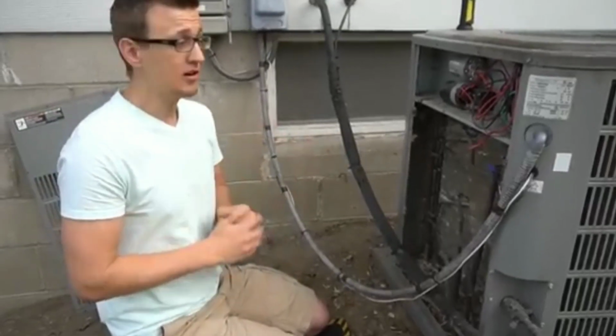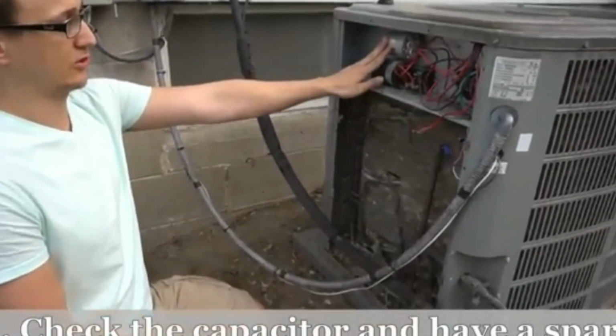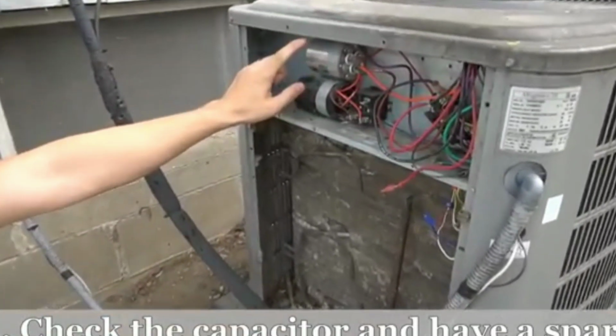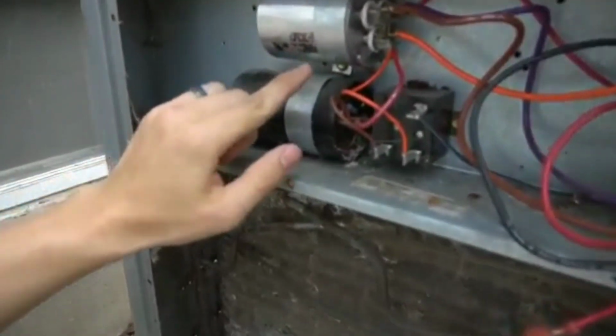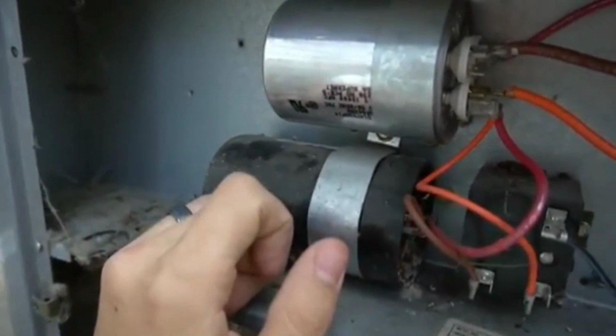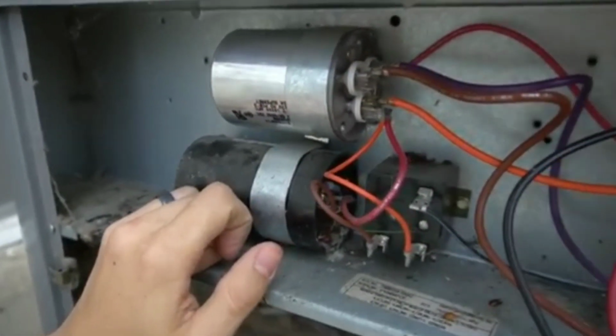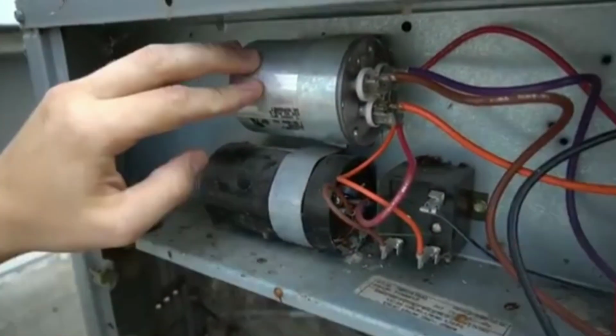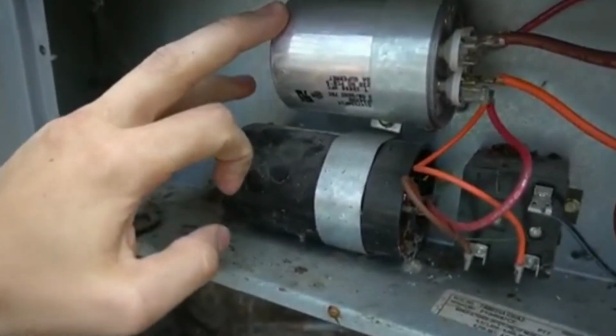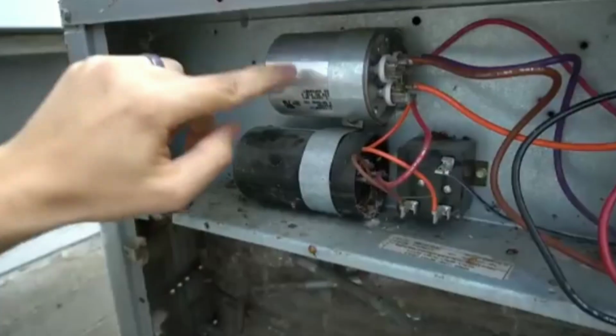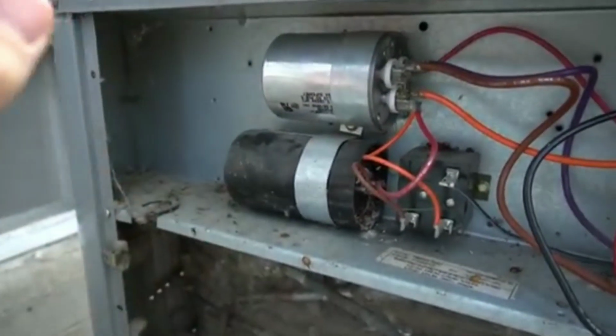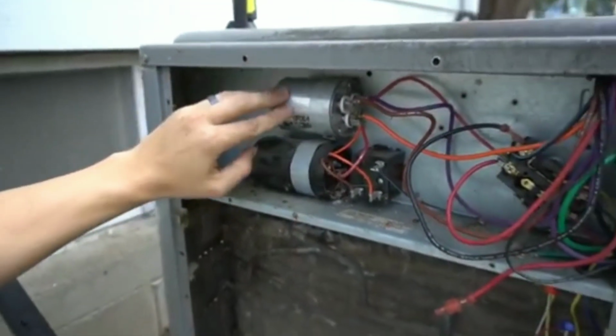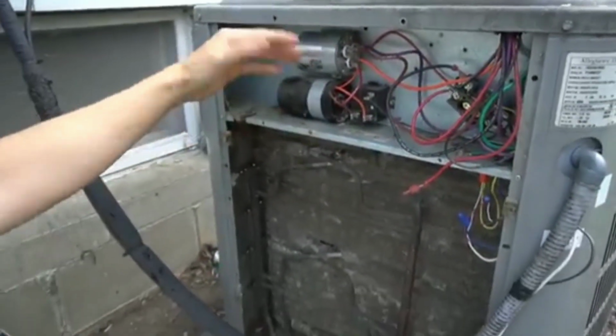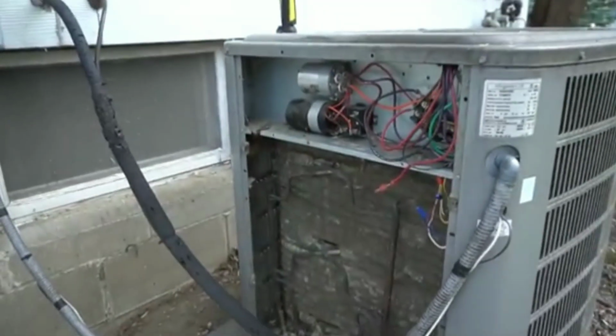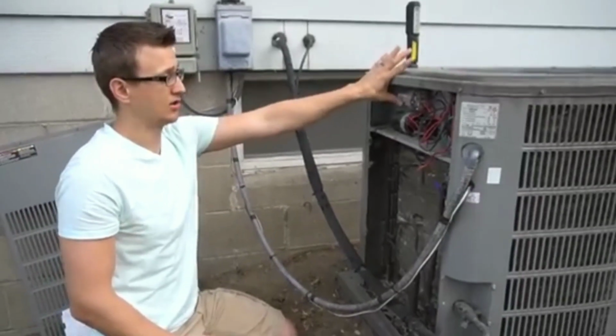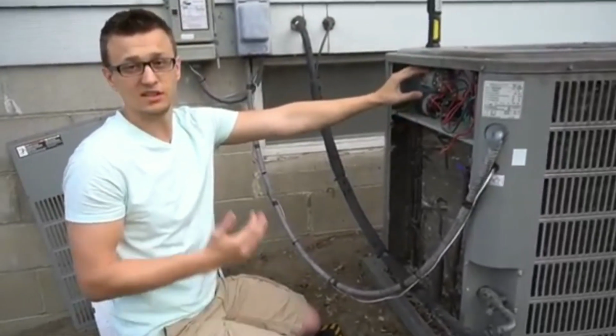And maintenance tip number 4 is to check your dual run capacitor, which is usually going to be a silver cylinder like this. It'll have a rating on it. I'm not going to take mine out, but I believe mine was a 40 by 5 microfarad capacitor. The most common AC problem, I have a video called Top 10 AC Problems. This is the reigning champion. He won first place by a landslide. So the most common air conditioning problem is a bad capacitor or a weak capacitor. So if you have a multimeter, check your capacitor at the beginning of the year because they are not eternal parts. They are pretty cheap components and they do fail often.